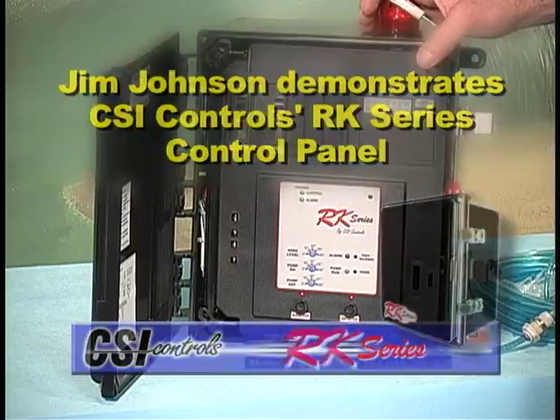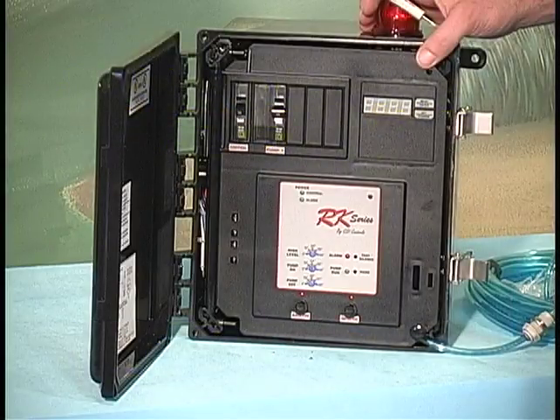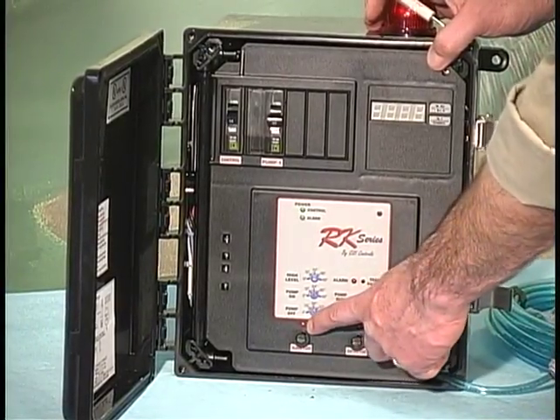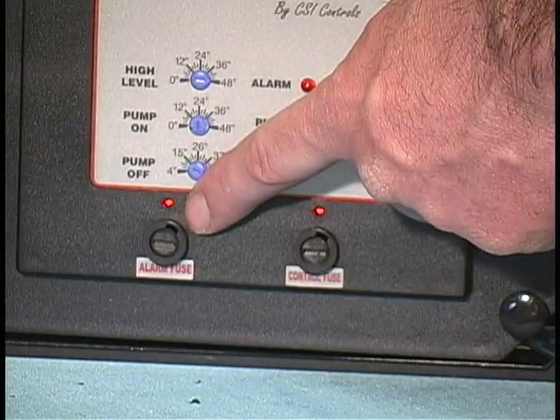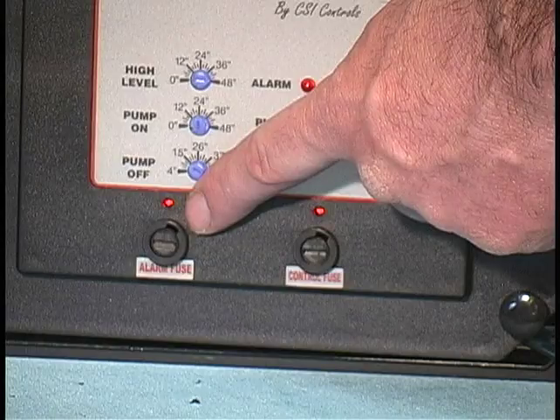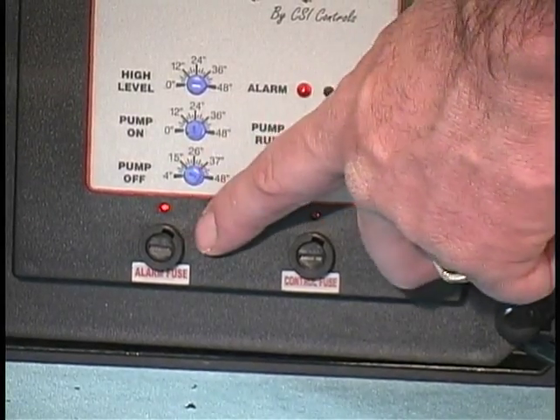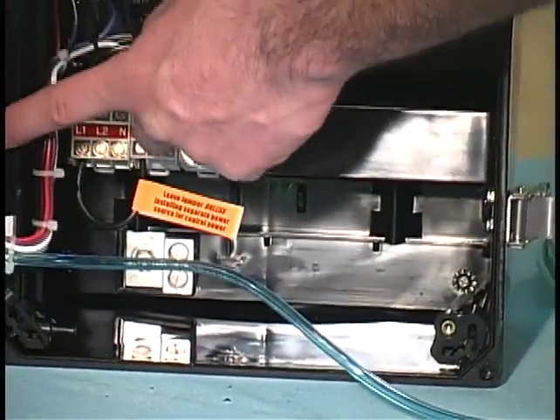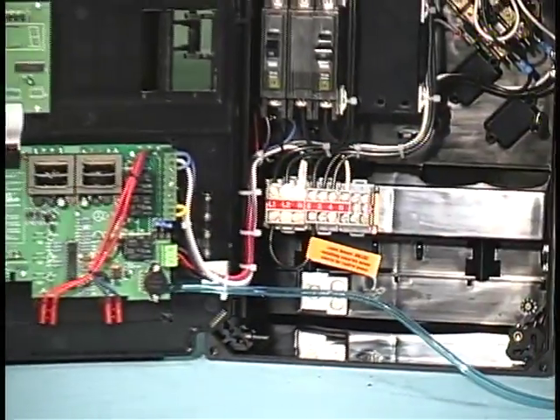Take it away, Jim. Some of the features of the panel: it has both control and pump breakers. You can get them with both control, alarm, and pump breakers. Both the alarm and control sides are fused. When the fuse blows, the little red LED light above the fuse holder turns red. So it's a troubleshooting feature if you lose one leg of either the alarm or control side, and that'll be very visual if the fuse is blown. The panel also comes with spare fuses on the back side of the faceplate.